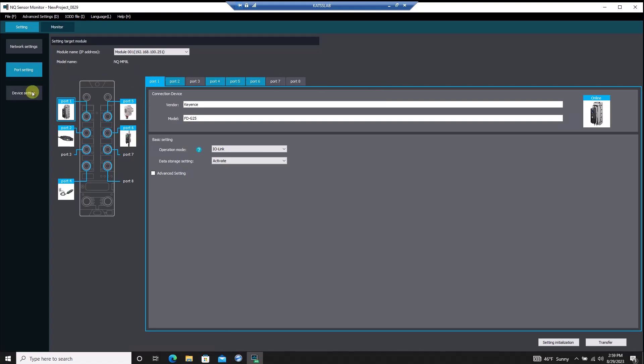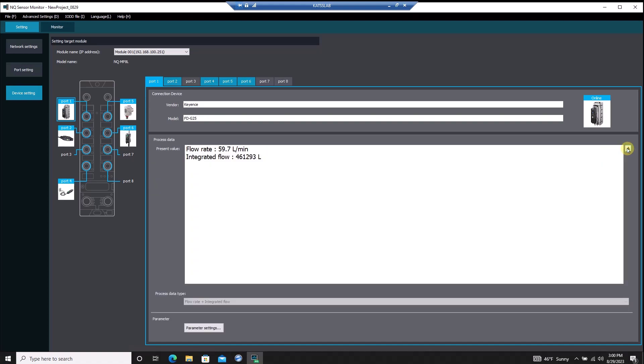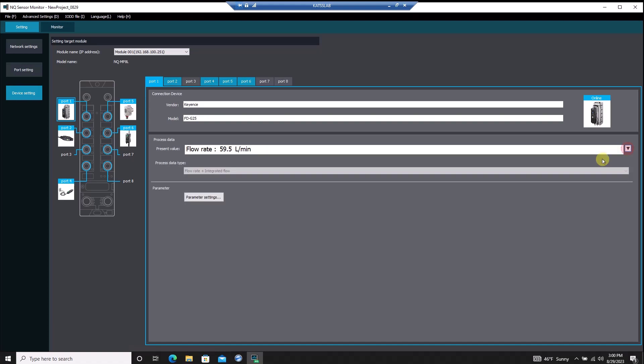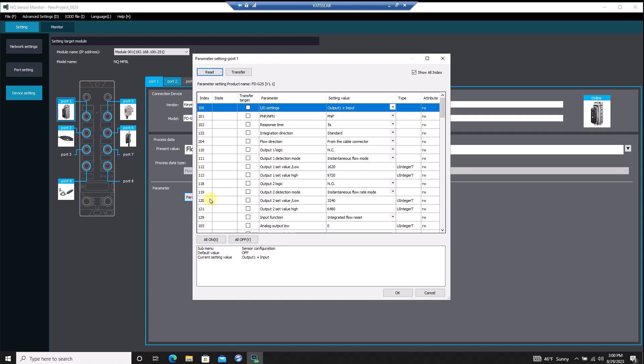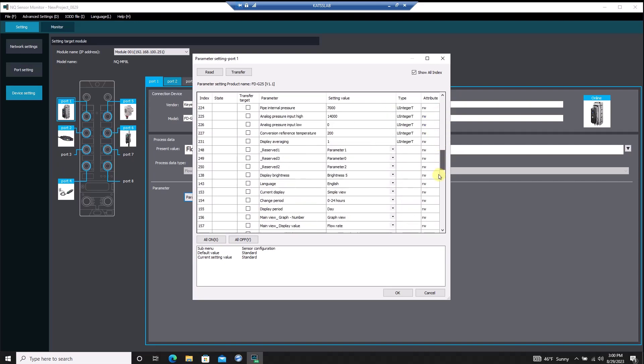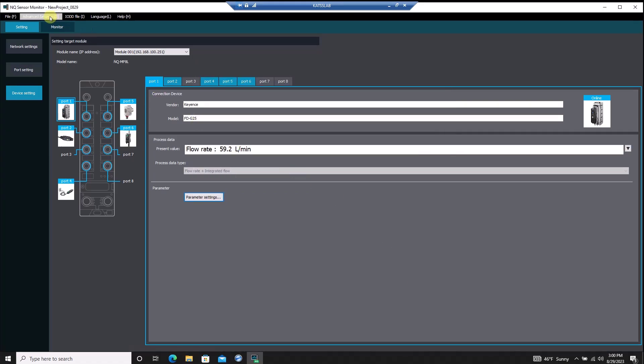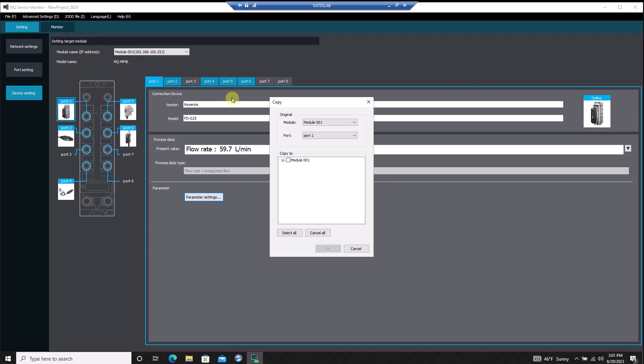In the Device Settings menu, we can monitor the process data that cyclically updates between the sensor and the NQ. Additionally, we can remotely configure an IO-Link device by entering the parameter settings. Here we can change settings on the device or issue commands, such as tuning or initialization, using the IO-Link service data. Once you've got a device configured, you can easily copy the settings from that device's port and paste the settings to another port, allowing the ability to set up IO-Link sensors in large batches.